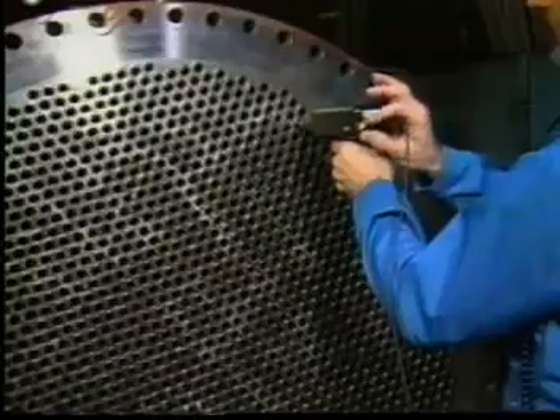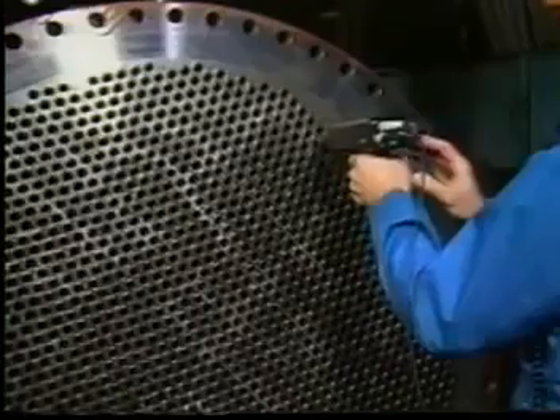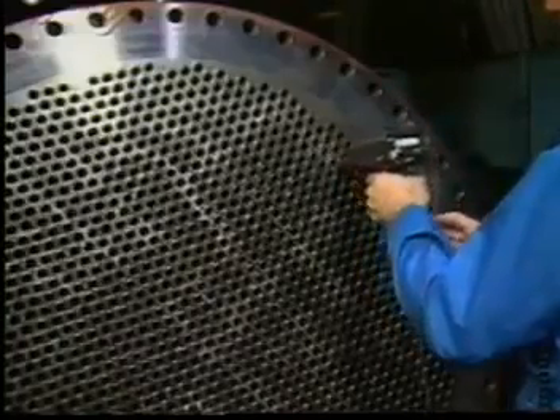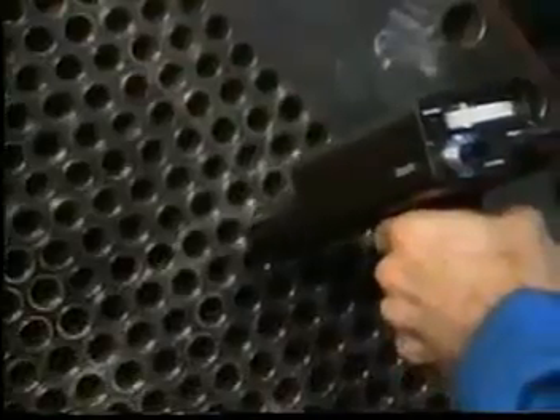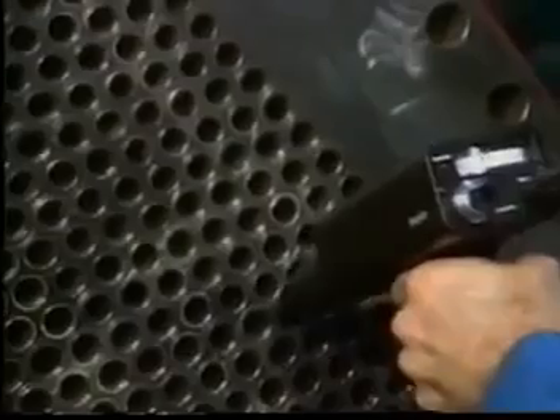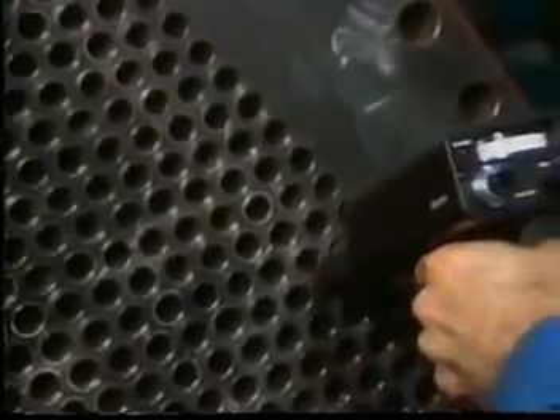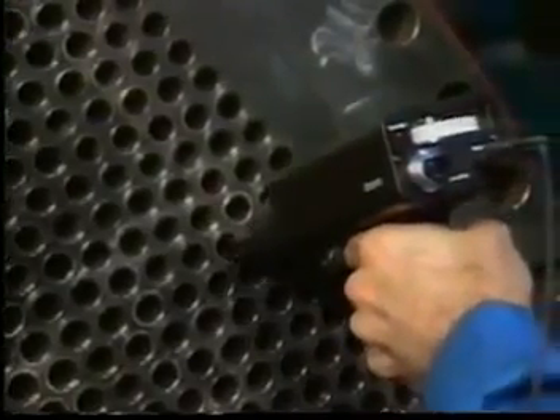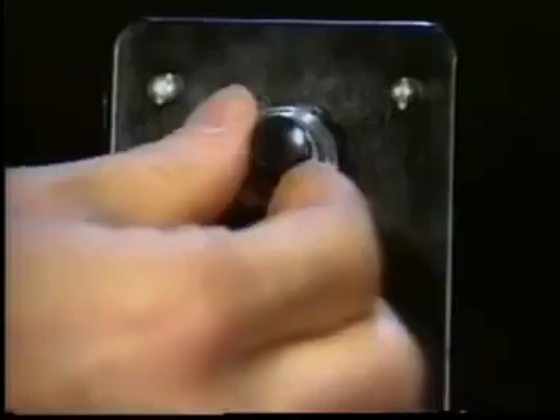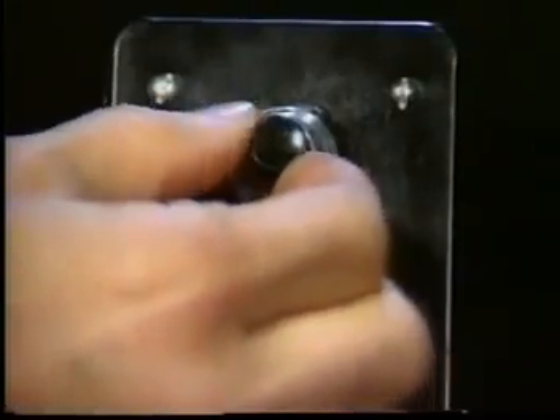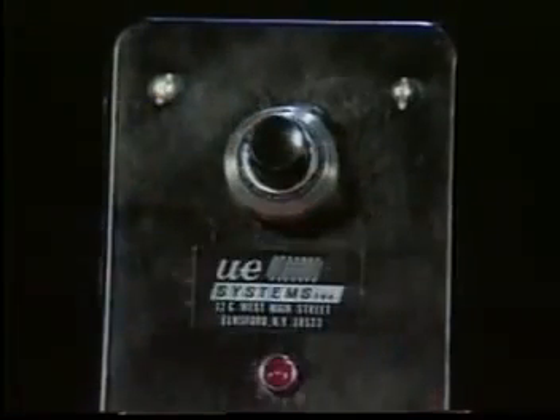Since tone generators are on top of peripheral tubes, they will be vibrated during testing of areas near the generators. For an accurate test, test one zone at a time. Reduce the ultraprobe sensitivity to read about 50 on the meter and scan for variances between tubes. Another variation may be to retain maximum sensitivity and reduce the warble tone generator's amplitude while scanning for these differences.